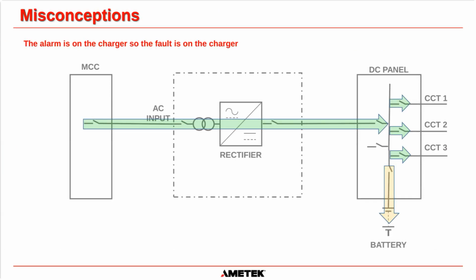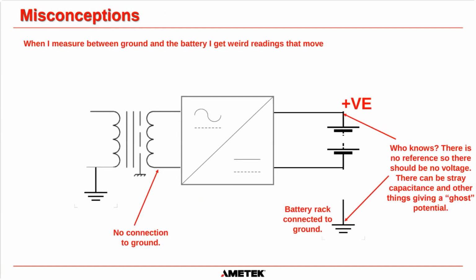So the last thing we'll do is we'll move on to some misconceptions. Okay, the first one is the alarm is on the charger, so the fault is on the charger. Basically, I've gone over that already. That's not the case. It's just because the alarm is on the charger, or the alarm in your control room may be connected saying that the alarm is coming from the charger. So everybody thinks the actual ground fault is in the charger.